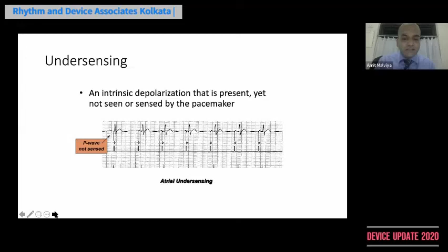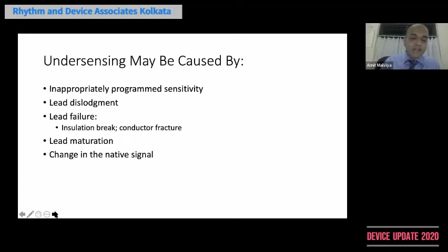When the pacemaker undersenses, it tries to overpace. Undersensing is usually caused by inappropriately programmed sensitivity. If you have programmed the sensitivity inappropriately, or there is a lead dislodgement, or failure of the lead in the form of insulation break or conductor fracture. Lead maturation means a lot of fibrosis around the lead tip, or change in the native signals. Native signals means the electrical signals originating from the heart.